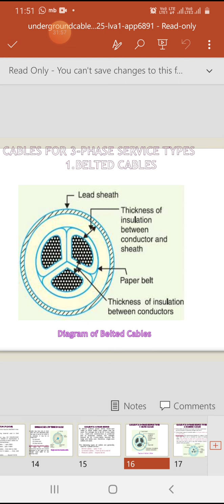The belted type construction is suitable for only low and medium voltages. The electrostatic stresses developed in the cable for these voltages are more or less radial across the insulation. However, for high voltages beyond 22 kV, the tangential stresses also become important, and these stresses act along the layers of paper insulation. The insulation resistance of paper is quite small along the layers, therefore tangential stresses set up leakage current along the layers of paper insulation. The leakage current causes local heating, resulting in the risk of breakdown of insulation at any moment. In order to overcome the difficulty, screened cables are used, where the leakage currents are conducted to earth through the metallic screens.